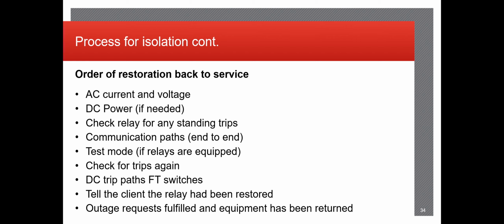So each time you put something in, you look at the relay, verify that there's no standing trips, there's no issues with the relay, and then you continue on in the correct order of operations. Once that is completed, you communicate with the client that the relay has been restored, your outage request has been fulfilled, and the equipment has been returned into service, meaning that there is nothing else to do other than cross your T's and dot your I's on your documentation, submit that and get out. The relay is back into service and the substation is good to go.